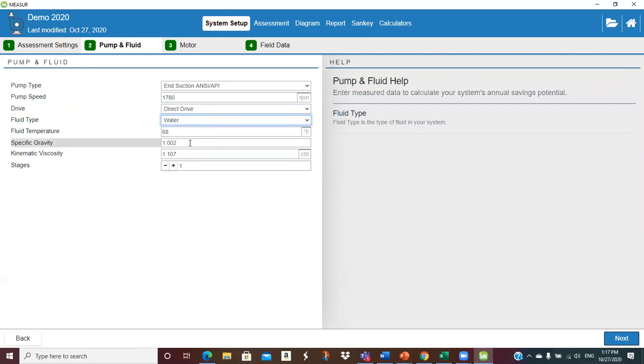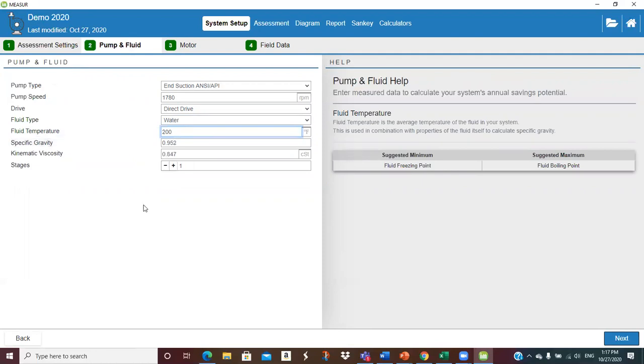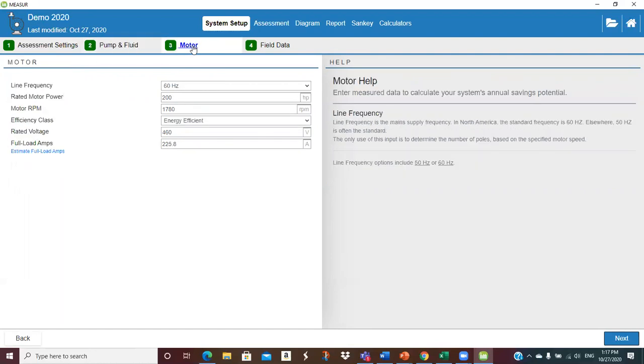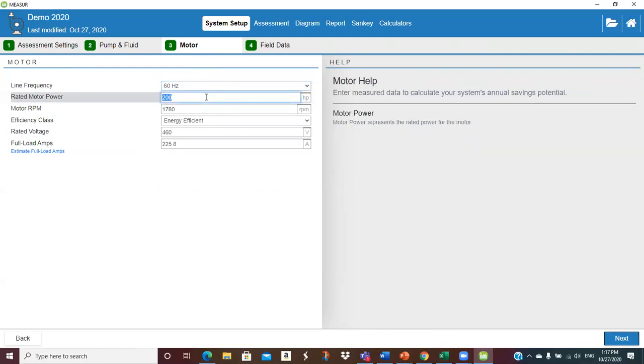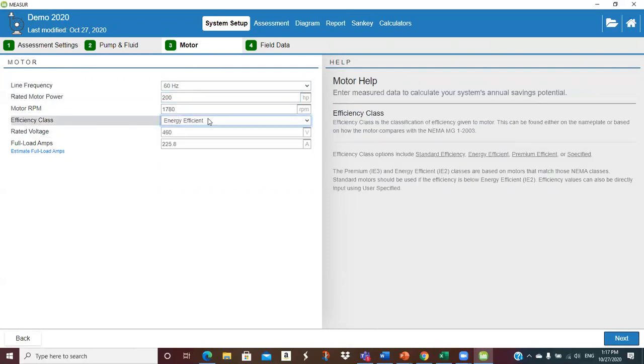Temperature, specific gravity, say, and let's see. There you go. See, it adjusts specific gravity for you. Now, that's like one of my test questions. I give you something and tell you to go calculate the specific gravity and see if you know what I'm talking about. Viscosity and all that. So you got that. There's your motor. 60 hertz, 50 hertz, that didn't change. Rated power, you just put it in. That's fine. RPM, different types, same stuff. Voltage, and then you can put in full load amps.